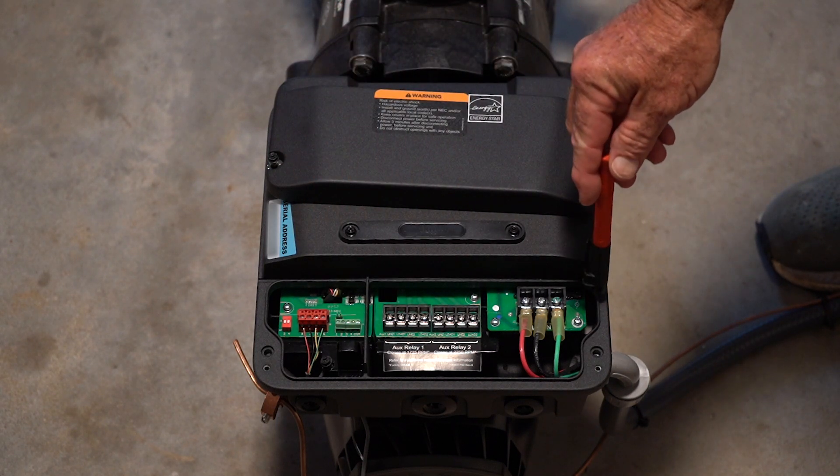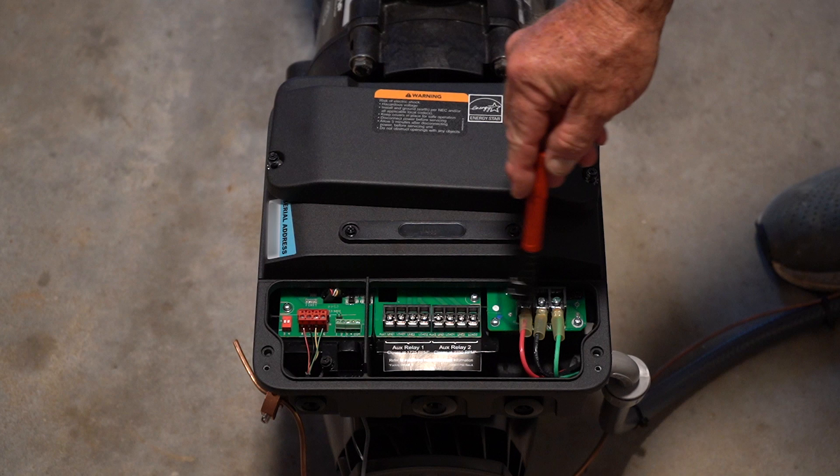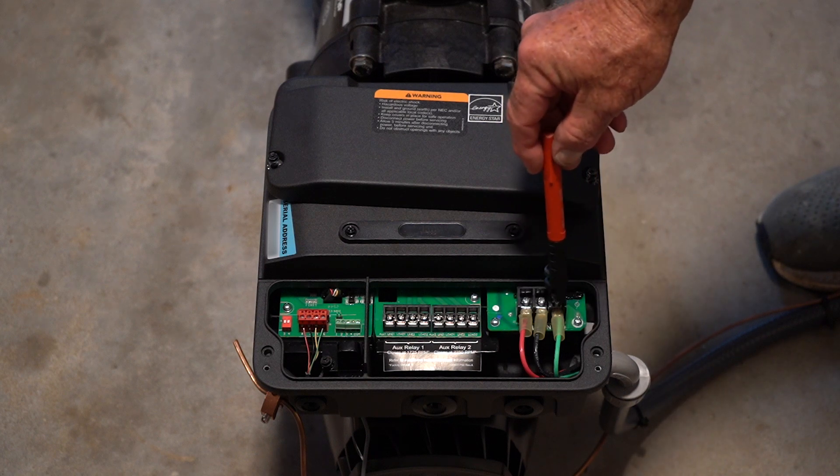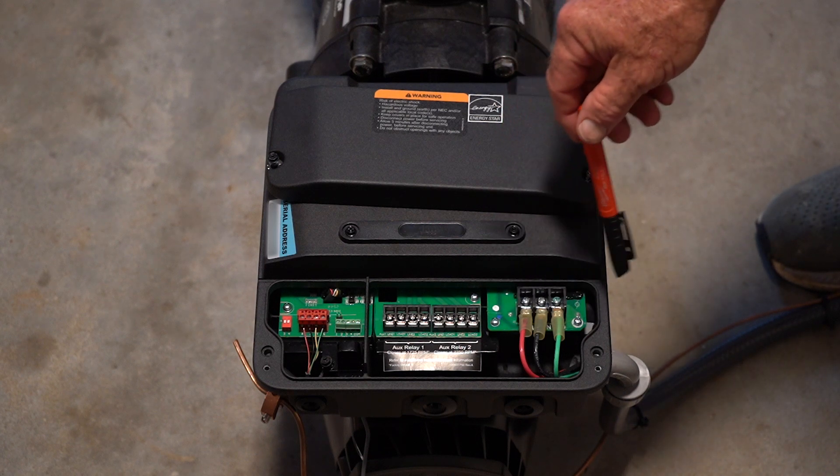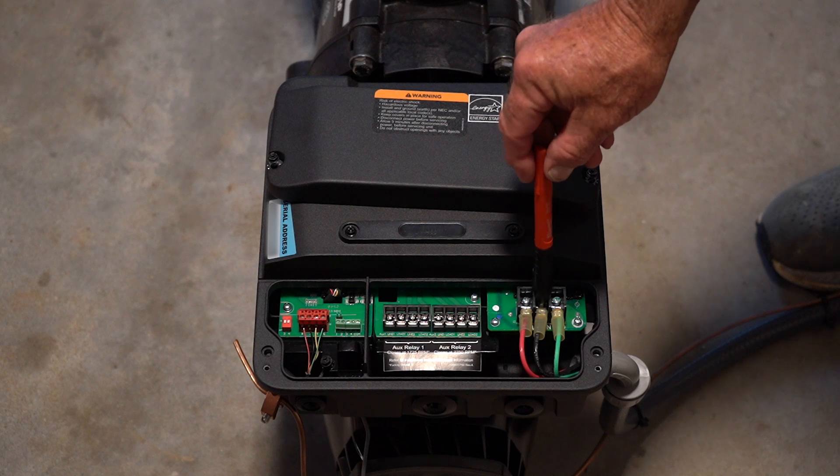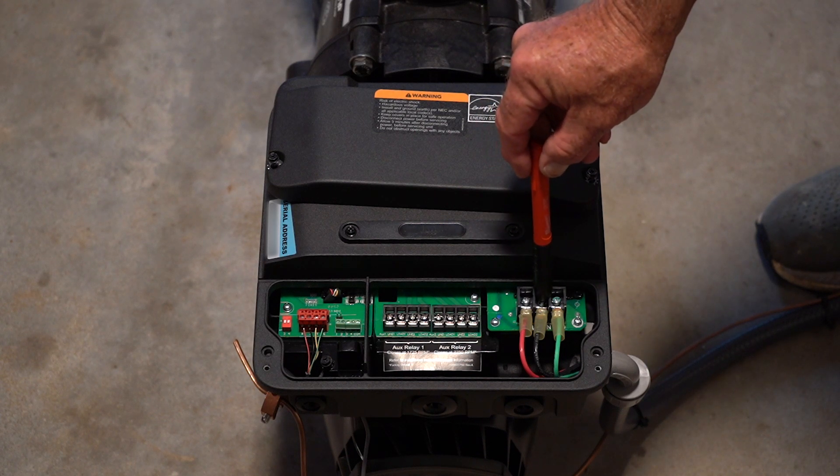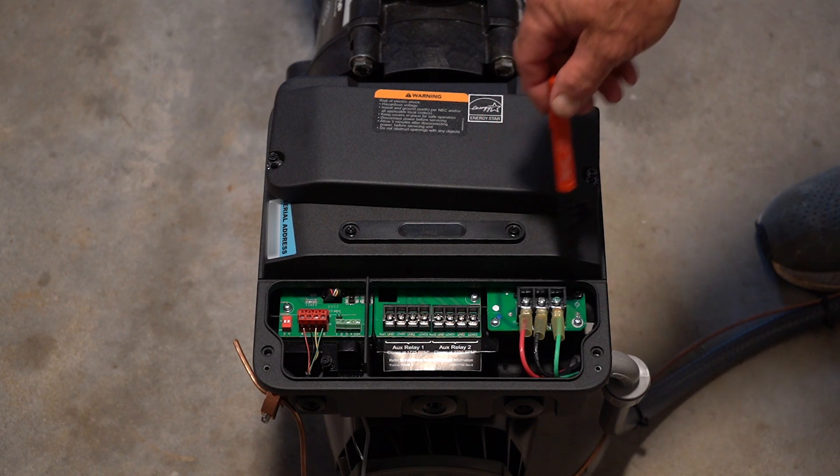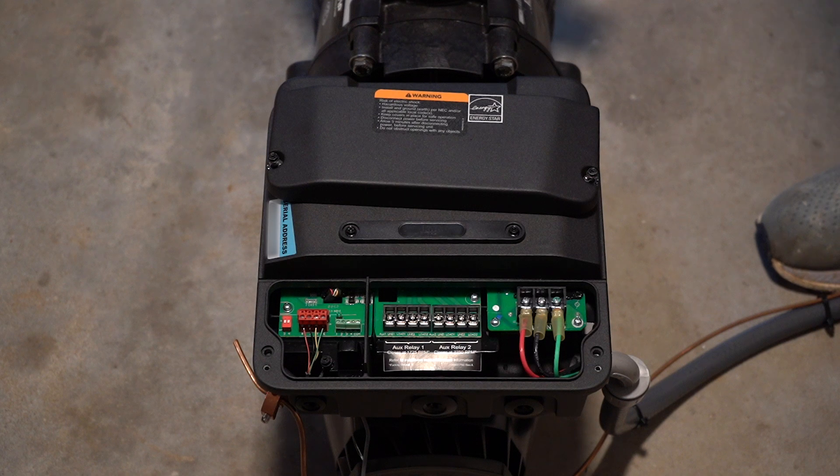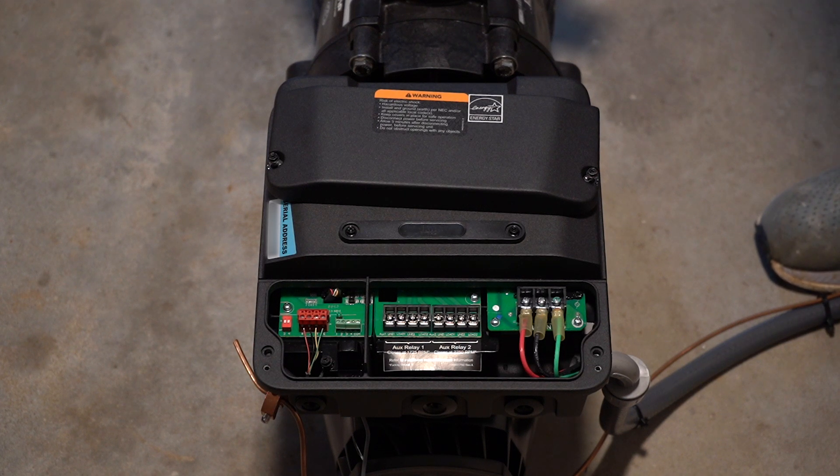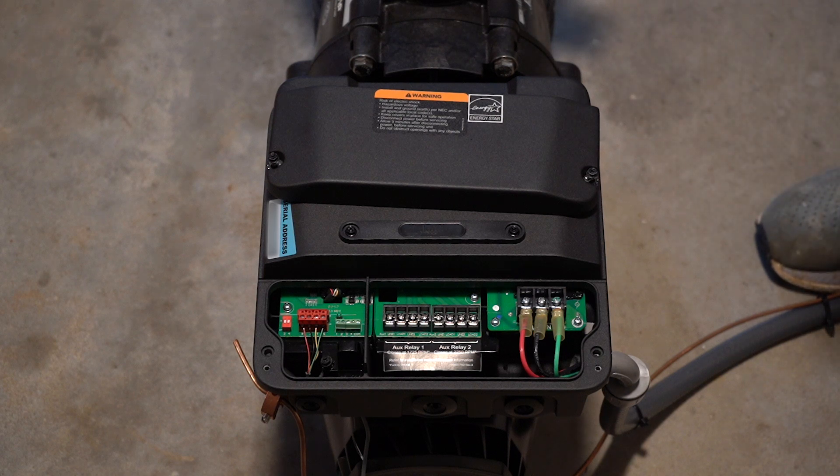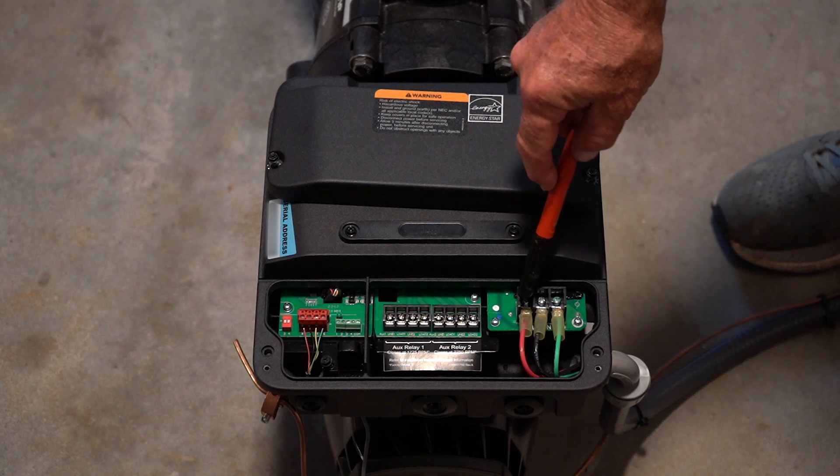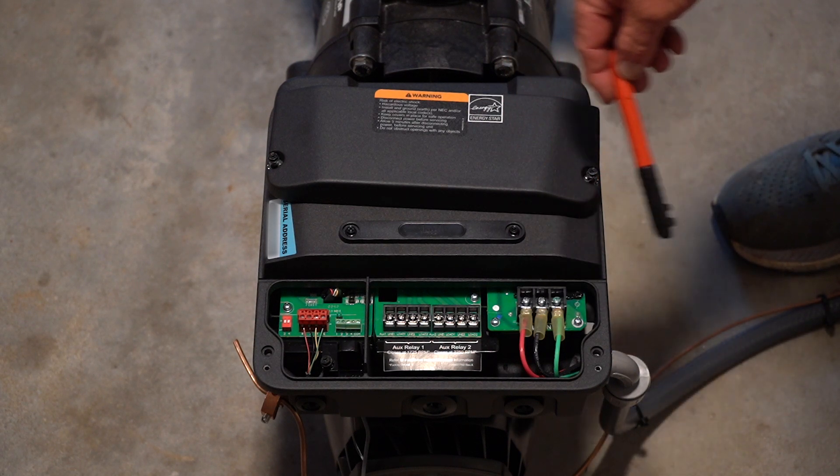It is so nice that you've got so much room to connect up your high voltage. So here we have our ground and we have our two lines, line one, line two. This particular pump must have 240 volts. It takes 20 amps. This is effectively a three horsepower pump for all intents and purposes. Power, power, ground.